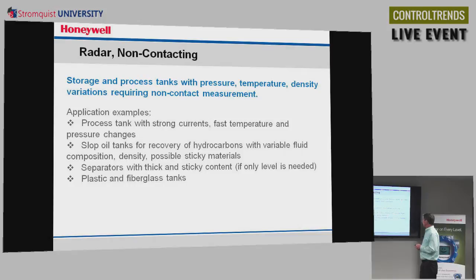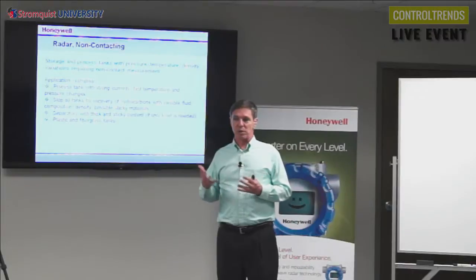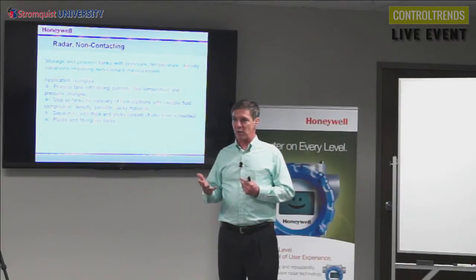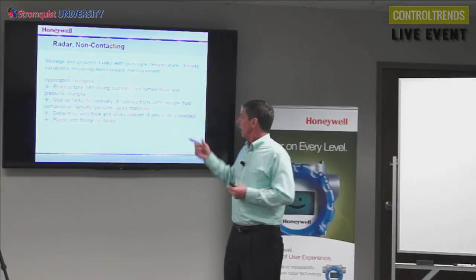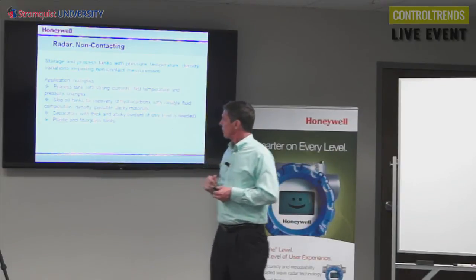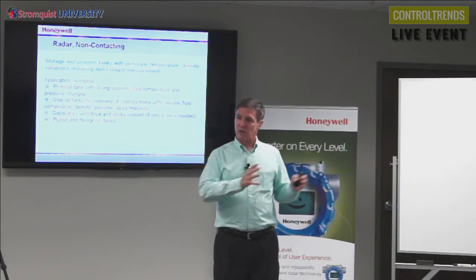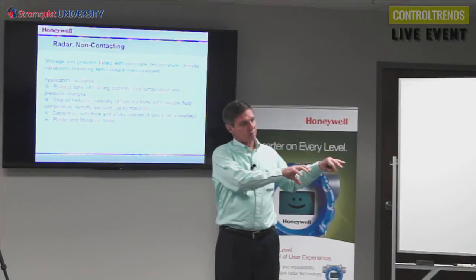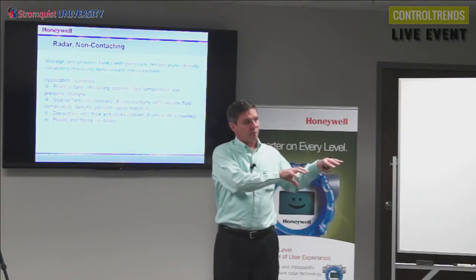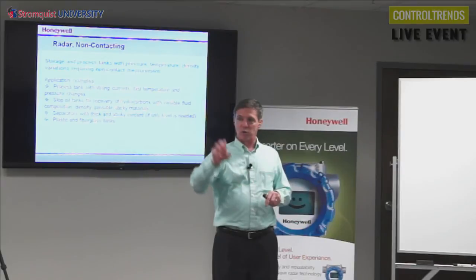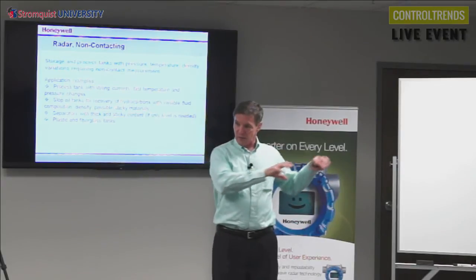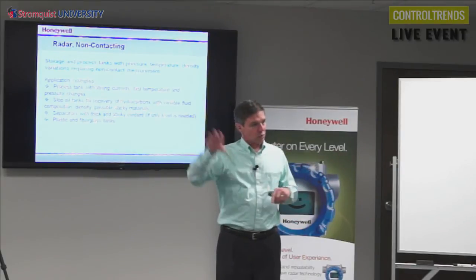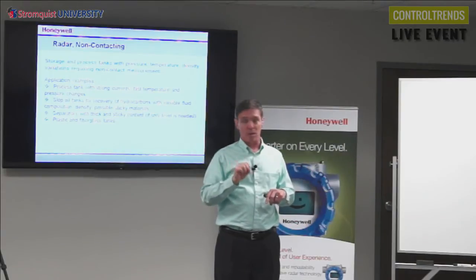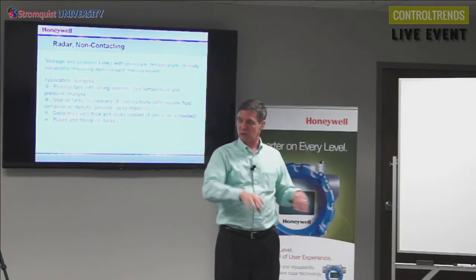Slop oil tanks, this is for the recovery of hydrocarbons that have variable compositions, because if the density is changing a lot, you can't use some of these other things like displacers, you can't use differential pressure. And a slop oil tank, this is kind of interesting, is when a company is pumping a product, let's say it's a liquid, liquid A, going through the pipeline and it's going to go into storage tank A. They pump product A, it goes into storage tank A, and then they want to pump product B over to storage tank B.